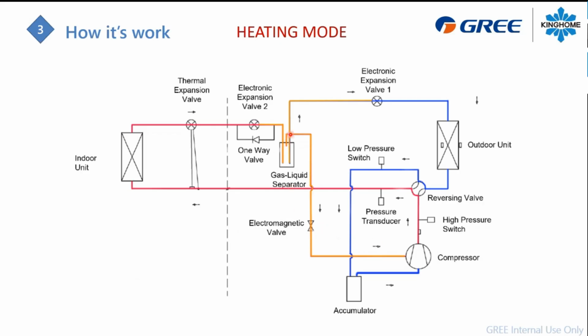Just the compressor here will just take some high temperature vapor and it will be introduced into the compressor. So you will see a compressor with 3 lines into it. So it's called a vapor injection directly in the base of the compressor. And this technology here will produce some heat in the base of the compressor. So the compressor can easily compress the refrigerant. So even if it's really, really cold outside, you will have a good pressure in your system to make sure you have enough heat in the indoor unit.